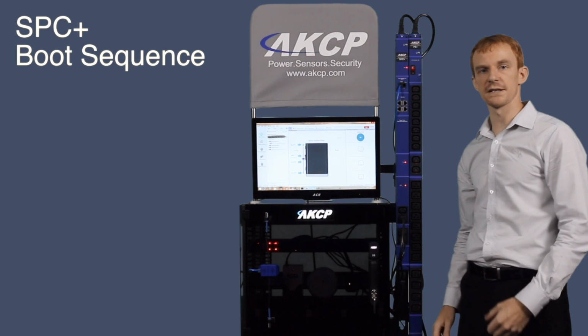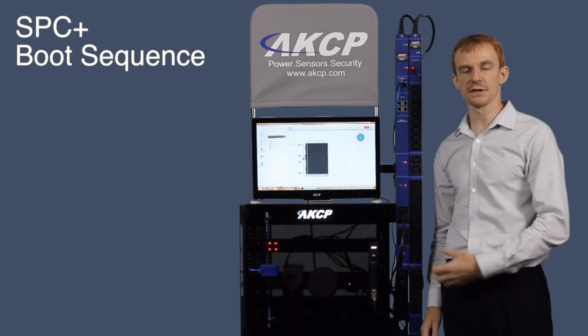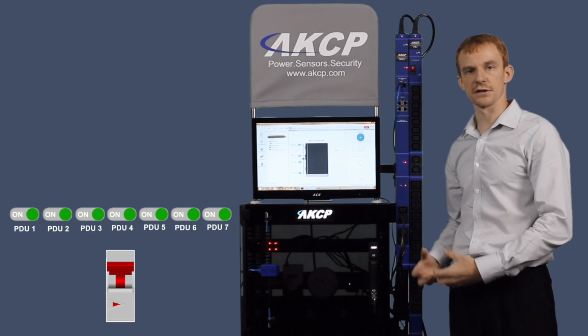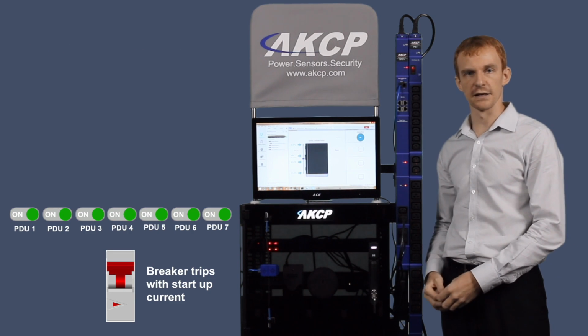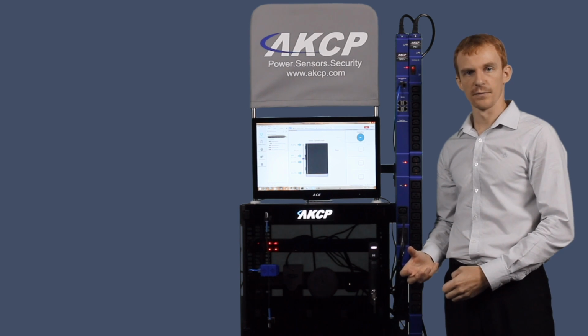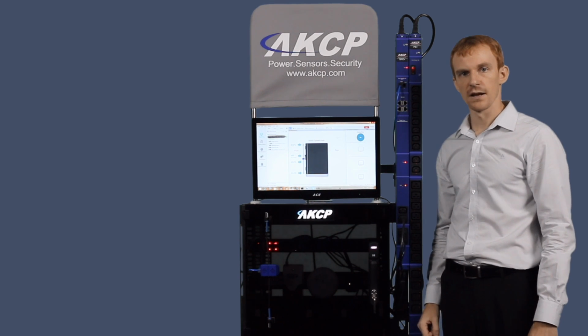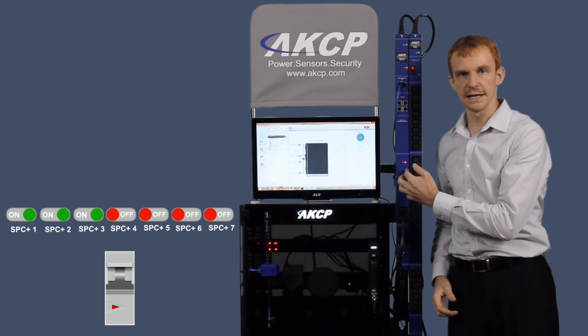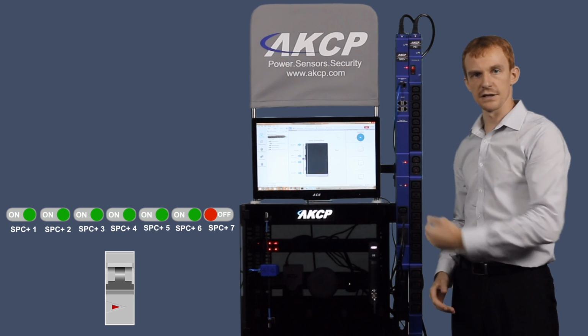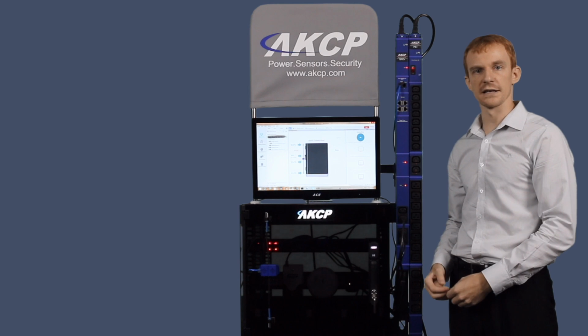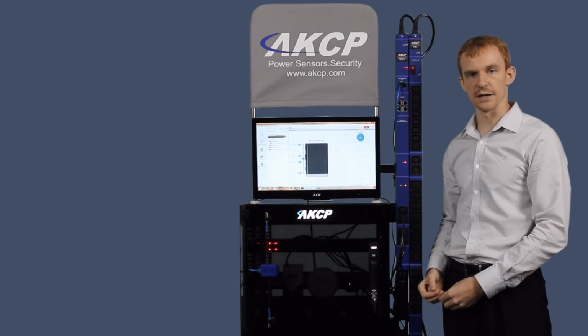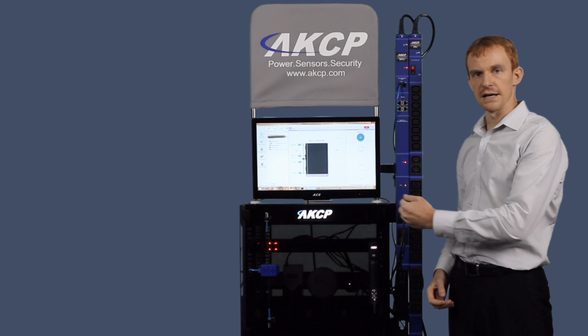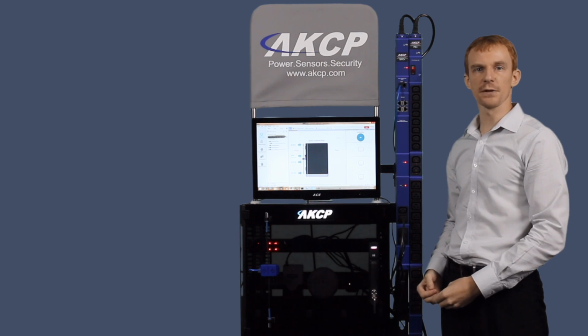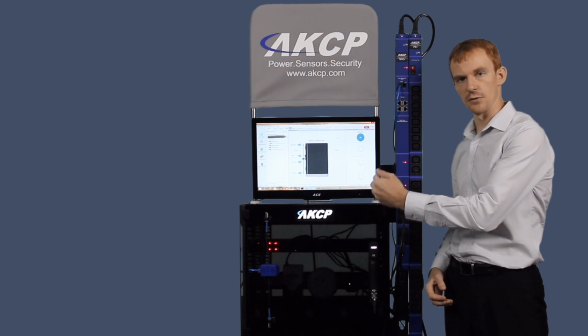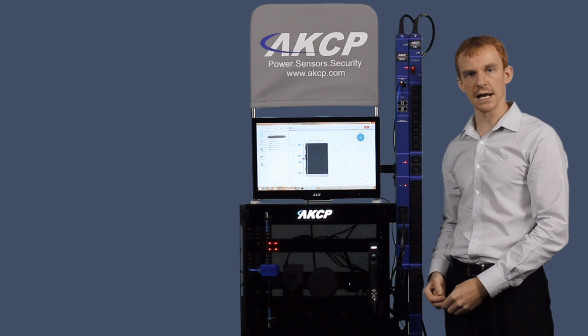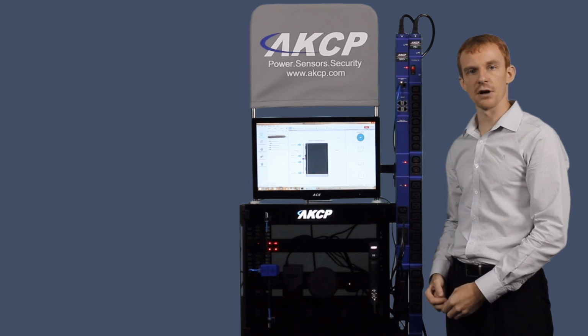A key feature of the SPC Plus is our patent-pending boot sequence technology. The sudden current surge caused by powering up your data center can cause your circuit breakers to trip, bringing down the whole data center. We can program the relays in each SPC Plus device to turn on in sequence, therefore avoiding this sudden current surge which will trip your main breakers. This boot sequence is distributed to each SPC Plus remote device, so even in the event of your main gateway going down or loss of communications, the boot sequence will continue to operate as normal.